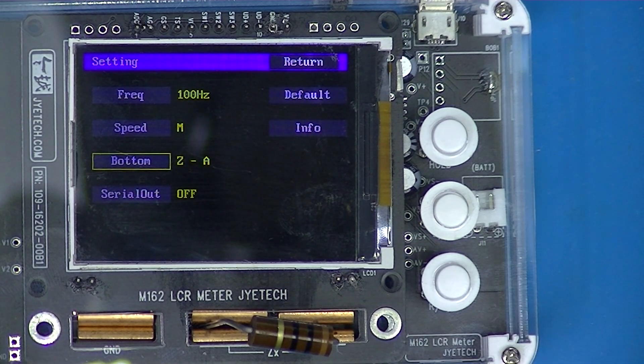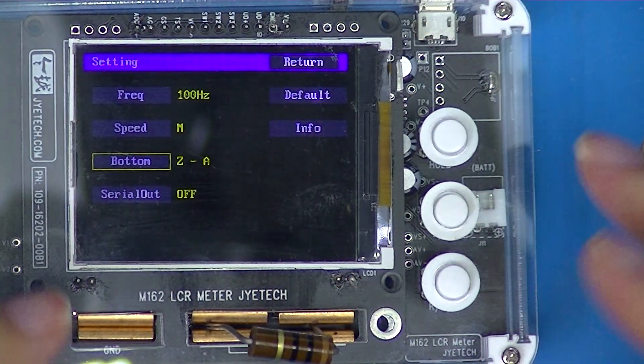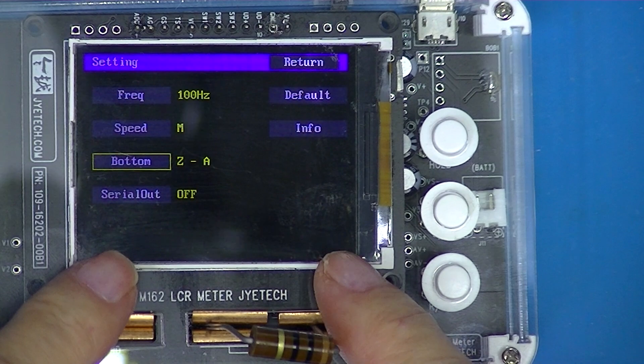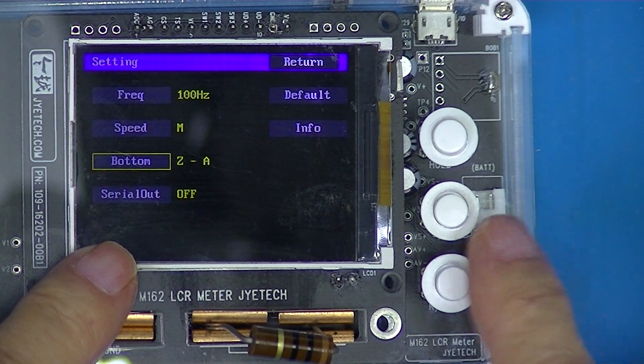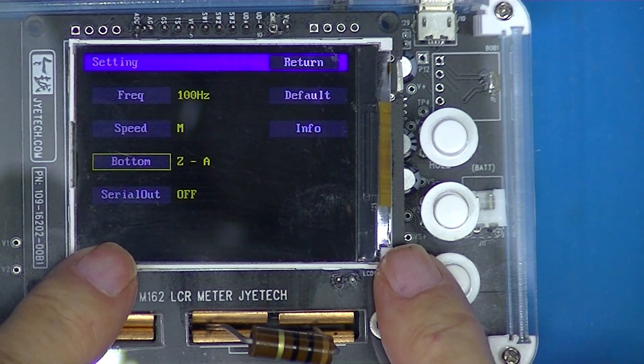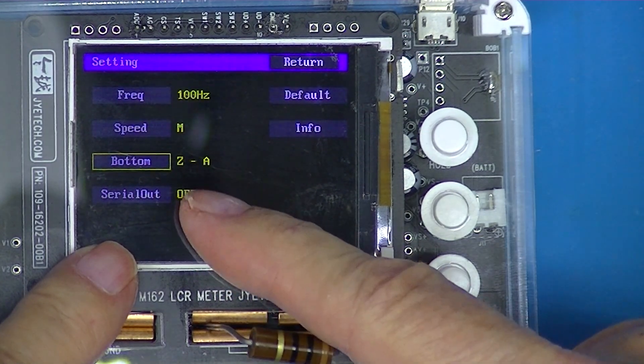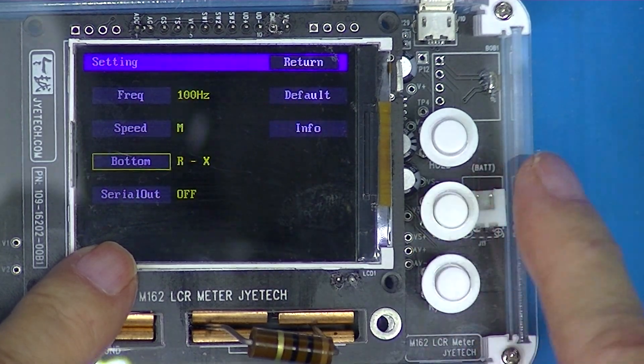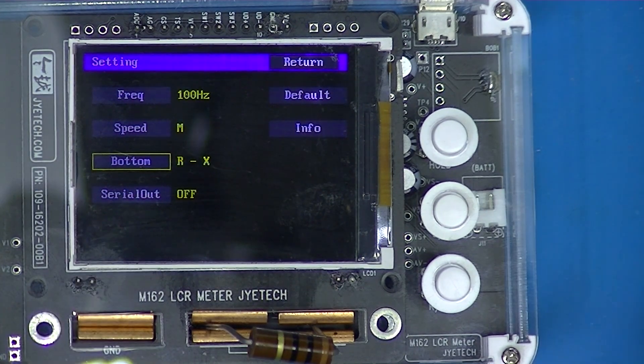Moving down to 'bottom' — that's the information displayed at the bottom of the measurement screen. That's information about the complex number series: ZA is modulus and phase angle, and RX is resistance and reactance.